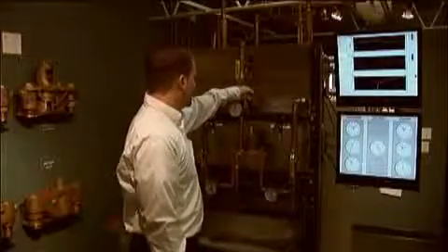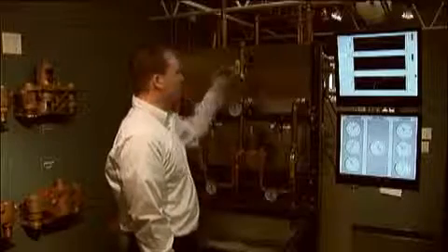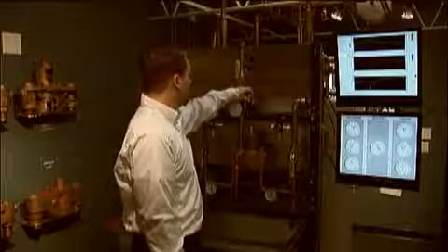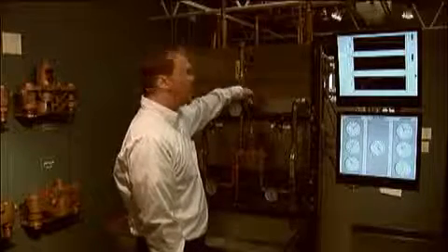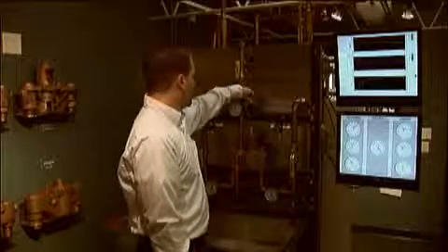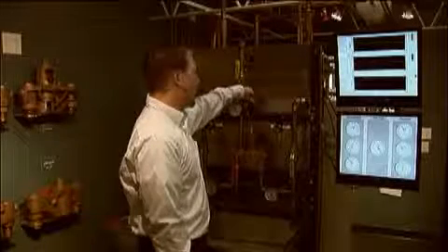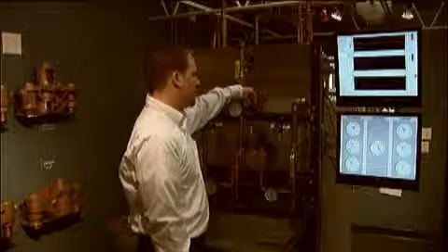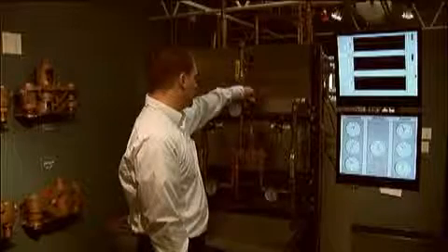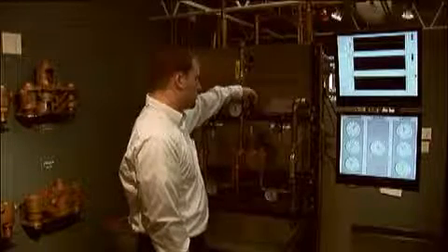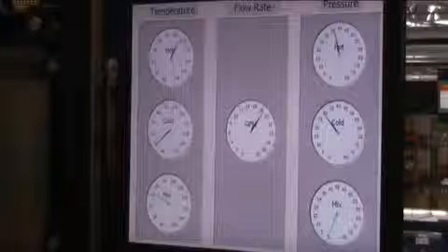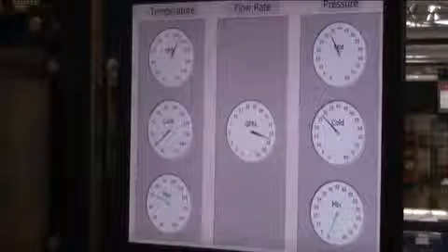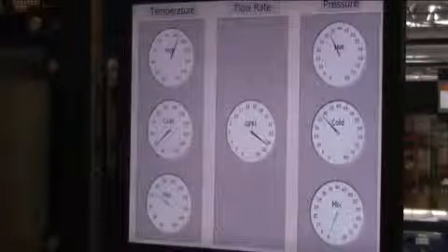To change temperature in a mixing valve is very easy, just with a common tool. Through the top, a 5/16" Allen wrench. If I turn in a clockwise direction, I will get a cooler setting. If I turn in a counterclockwise direction, I will increase the temperature.